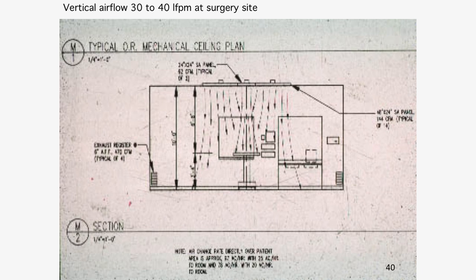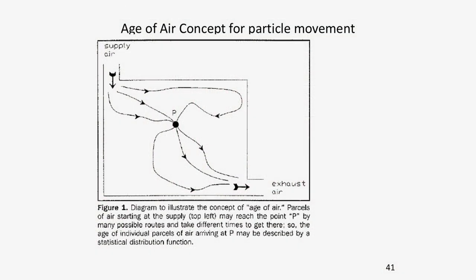What we're trying to do in slide 41 is really control the particle. Keep the particle moving. The longer the particle stays in that room, the worse off that ventilation is. So the better the ventilation, the shorter the age of air. In other words, if we can move air out of the operating room at the surgical site...